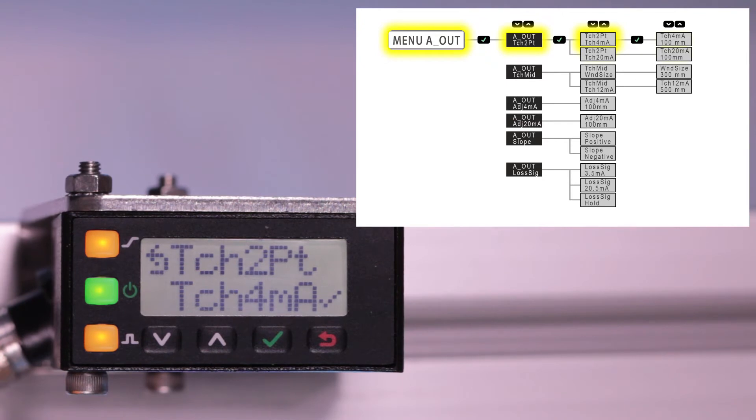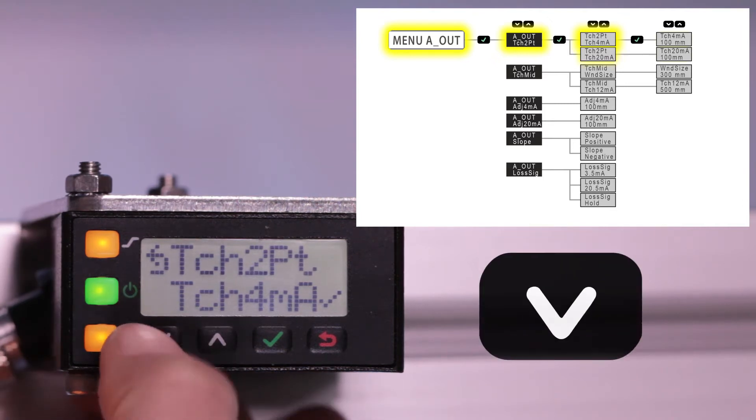When using 2-point Teach, the 4 and 20mA limits are taught separately, so it is possible to teach both limits or just reteach a single limit while leaving the other unchanged. The first option seen within the Teach 2-point menu is Teach 4mA. Click down to Teach 20mA.